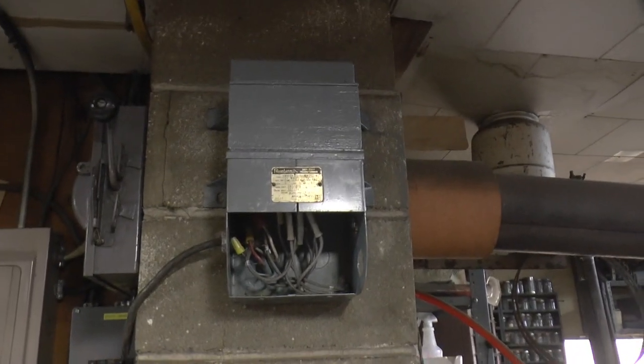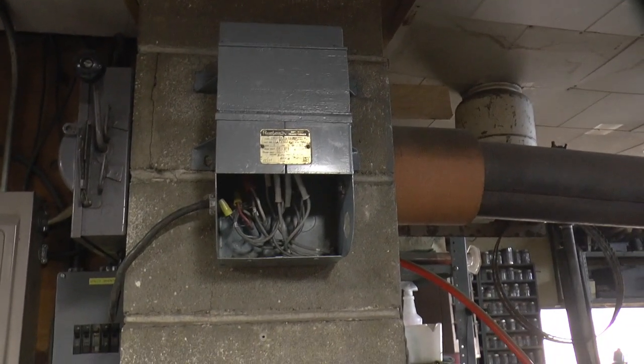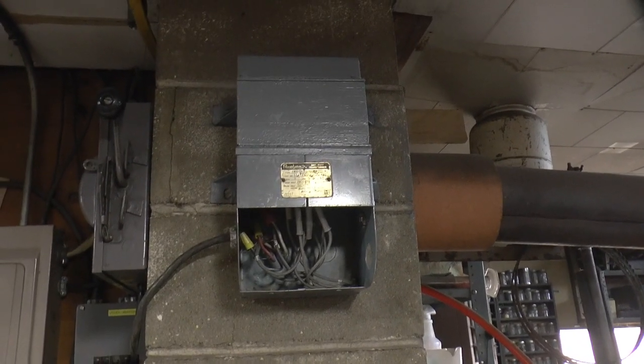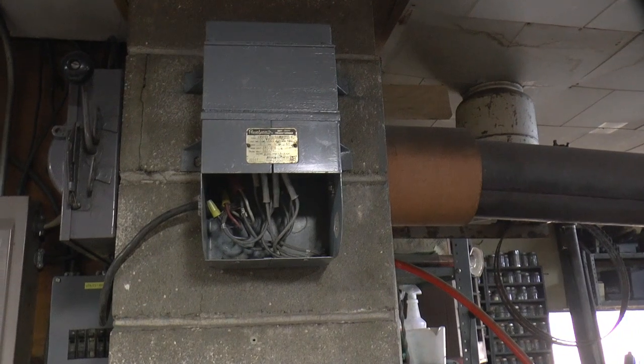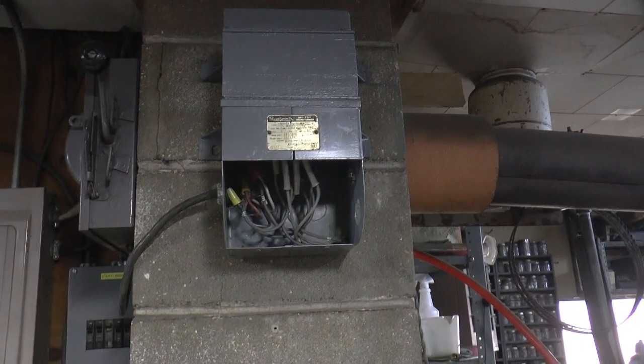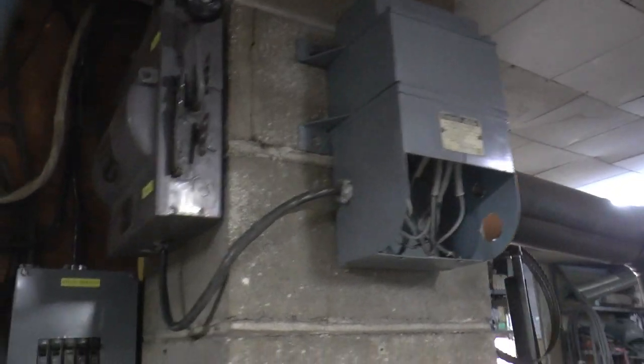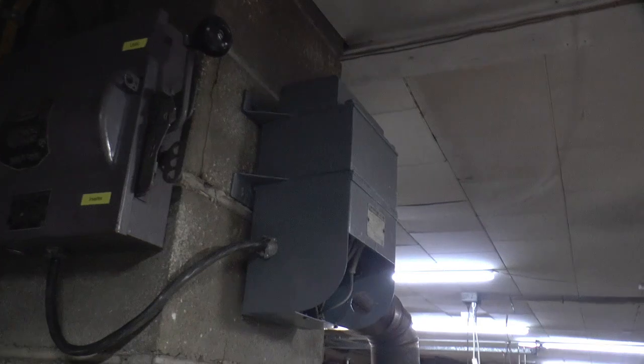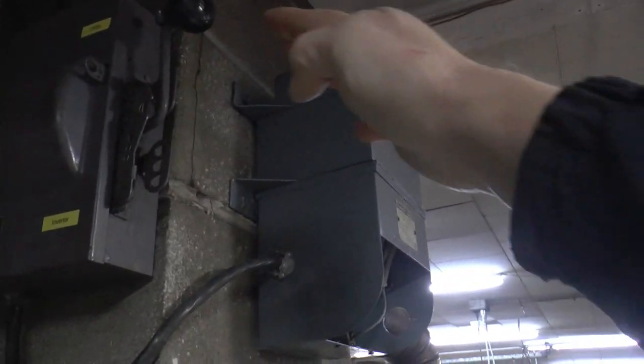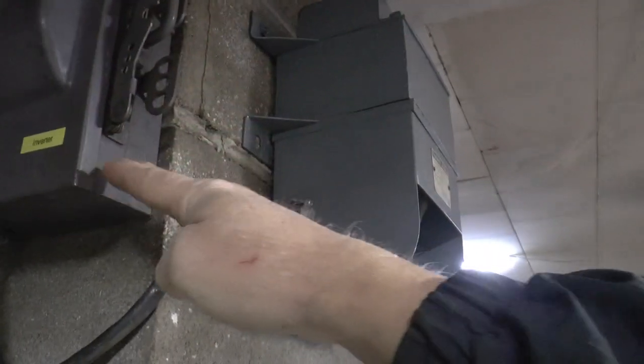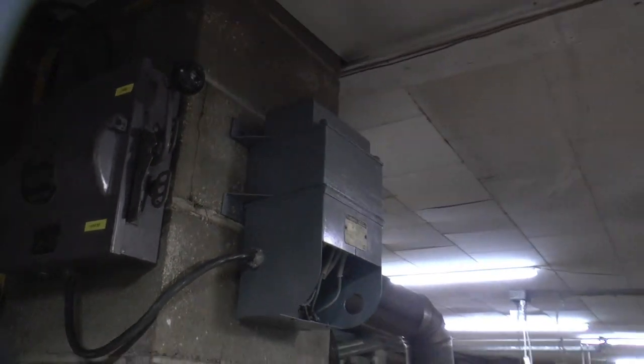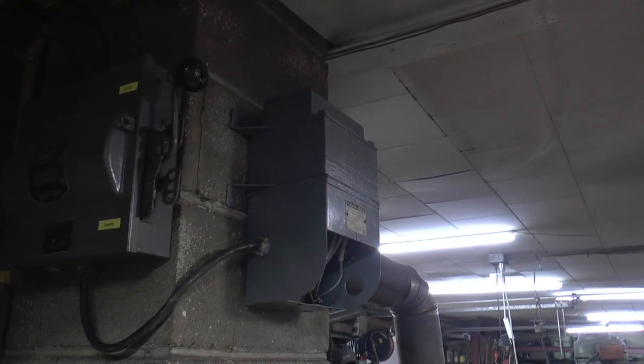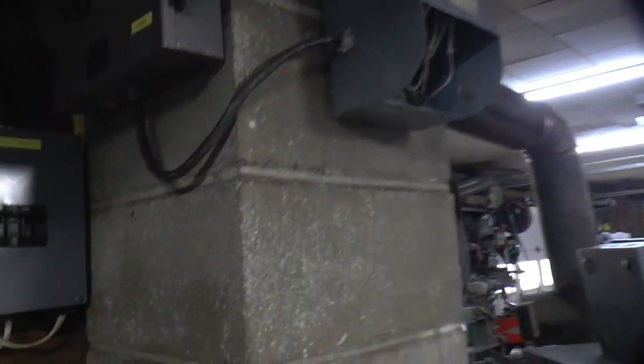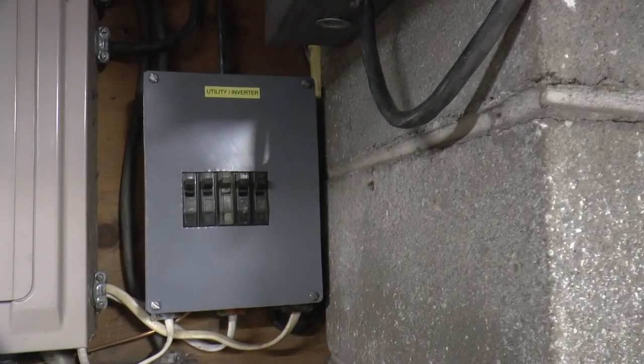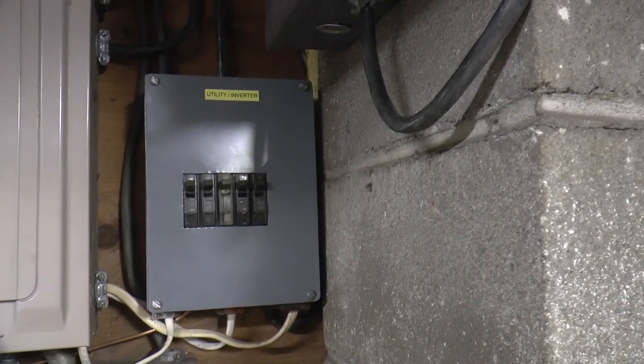This is block, so, and I have a 3 kVA transformer, not an autoformer, it's a transformer, and I have it wired for 220 in, 220 out, and it's going over here to a transfer switch, so I can run utility with it in this position, and if I put it down here it switches over to the inverter. I'm switching all 3 legs, and I put all the circuits that I want to switch over here, which is all the 120.